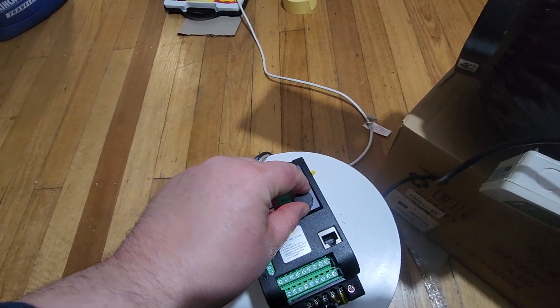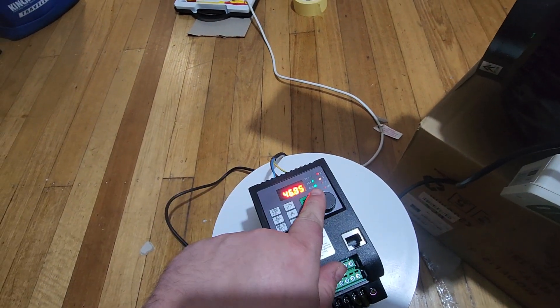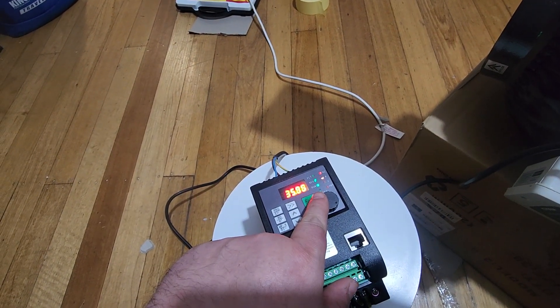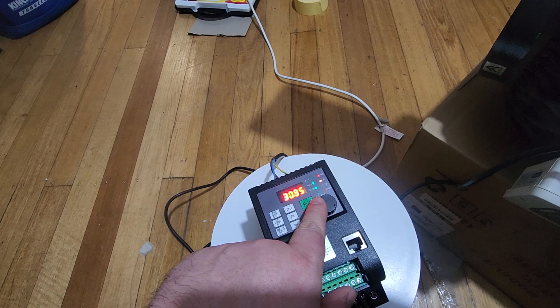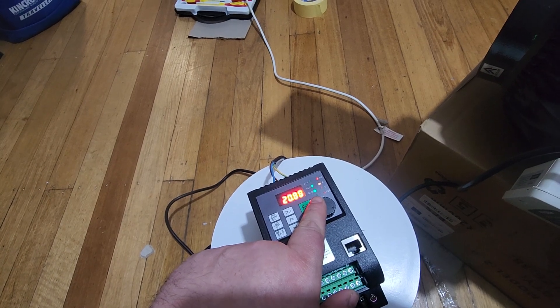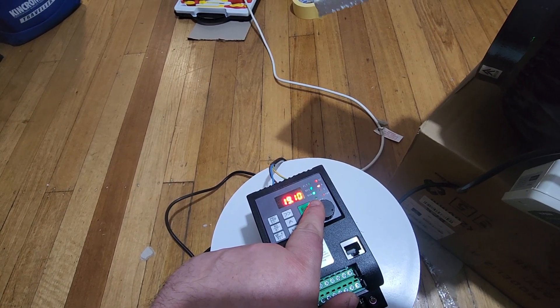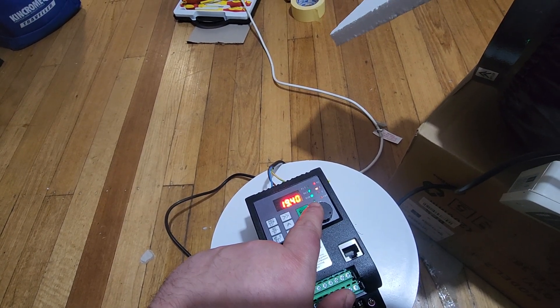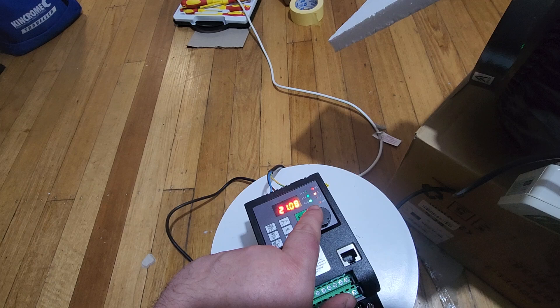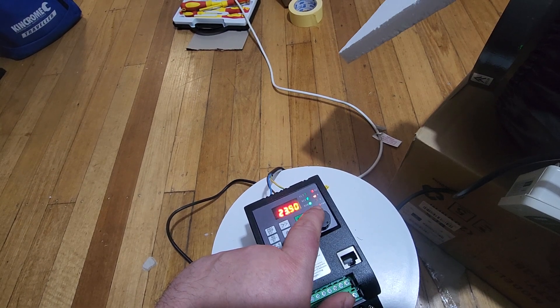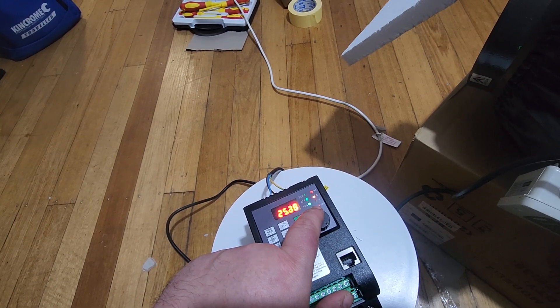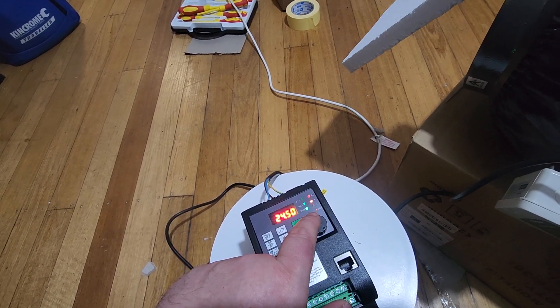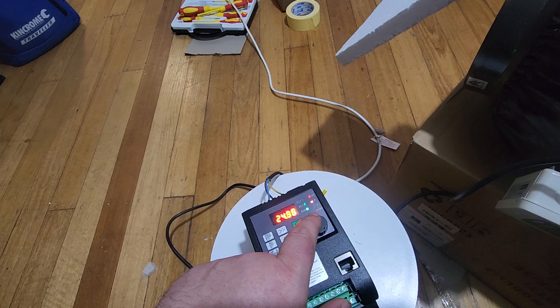So I'll reduce that down to about 25Hz again, it'll run at 19Hz but it won't start below about 24Hz or so, the fan just won't start.